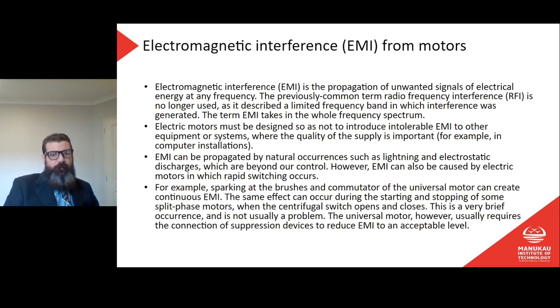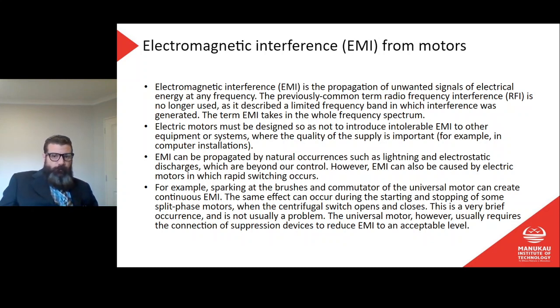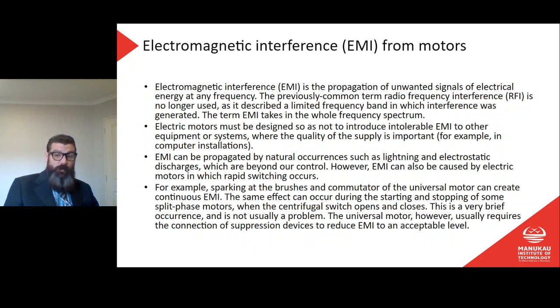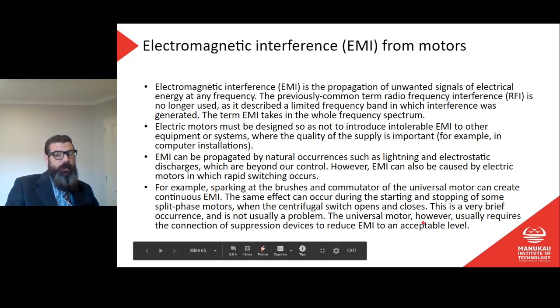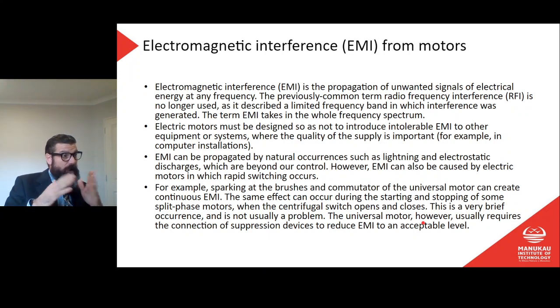Electromagnetic interference from motors: EMI is the propagation of unwanted signals of electrical energy at any frequency. Electric motors must be designed so as not to introduce intolerable EMI to other equipment or systems where supply quality is important, for example computer installations. EMI can be propagated by natural occurrences such as lightning and electrostatic discharges, but it can also be caused by electric motors where rapid switching occurs. Sparking at the brushes and commutator of the universal motor can create continuous EMI. The same effect can occur during the starting and stopping of some split phase motors when the centrifugal switch opens or closes, but that's brief and not usually a problem. The universal motor usually requires suppression devices to reduce EMI, because the brush and commutator switch the polarity of the incoming AC supply approximately 50 times a second.